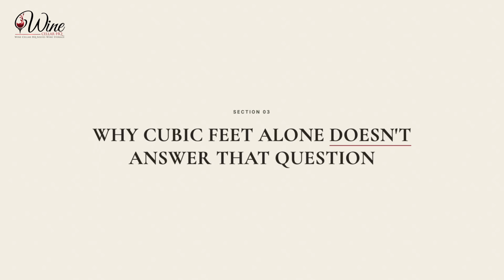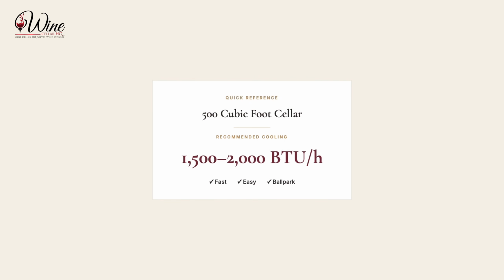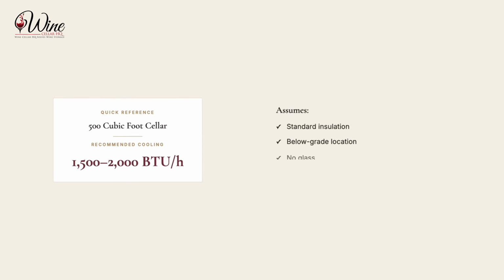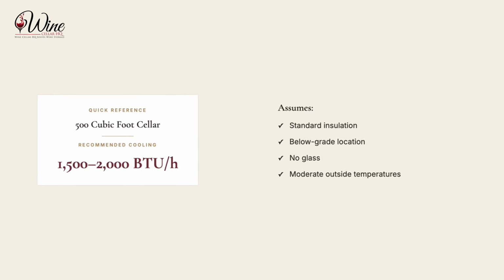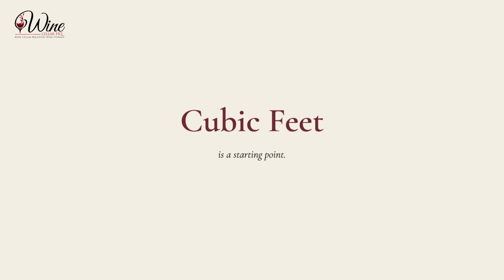You'll see a lot of quick reference charts online. Something like a 500 cubic foot cellar needs about 1,500 to 2,000 BTU per hour. Those aren't wrong exactly, but they're built on assumptions: standard insulation, a below grade location, no glass, moderate outside temperatures. The second your actual cellar looks different from that assumption, and most do, the real number can shift by 30%, 50%, even more. So cubic feet is a fine starting point for a ballpark. It is not a substitute for an actual calculation.